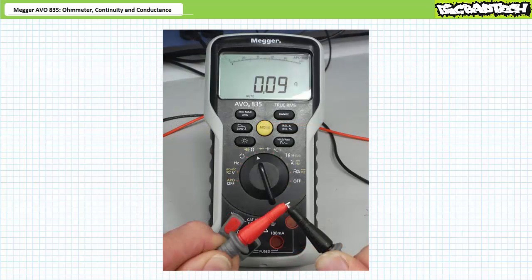When I touch the probes together, resistance plummets, indicating the test leads present an extremely low resistance path. This is an excellent way of function testing the leads. Leads with a break would indicate an open circuit and would not be suitable for testing the resistance of other elements.